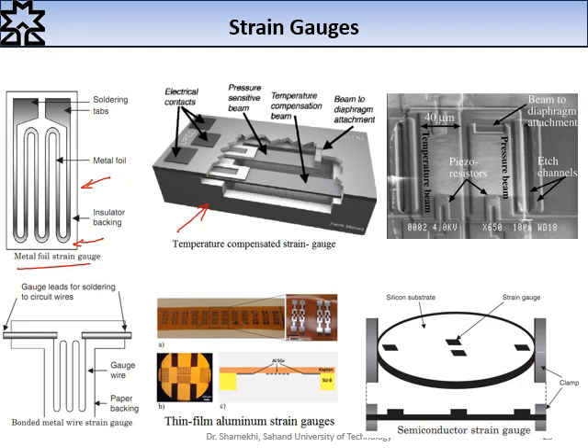And the second element is also a strain gauge, but this element is not connected to the diaphragm. The pressure will be measured by this one, and this second strain gauge is only for temperature compensation. The first one is for measuring the pressure, and the second one is only for temperature compensation.